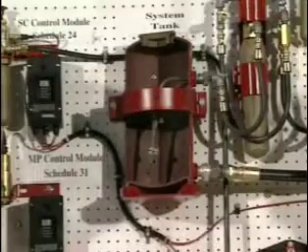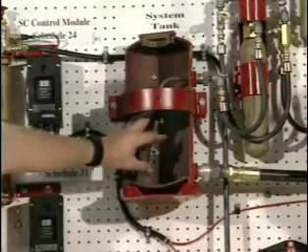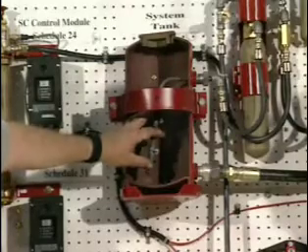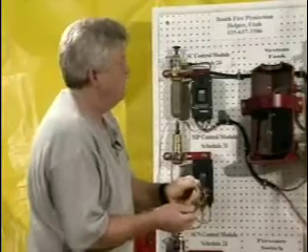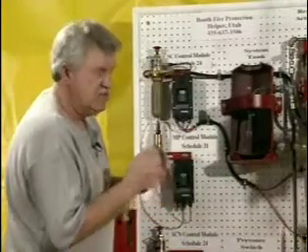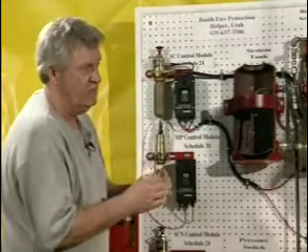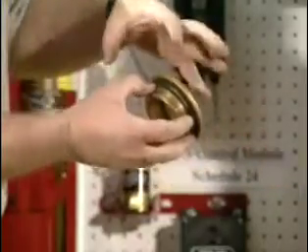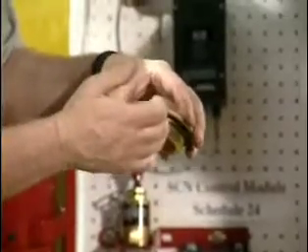Right. And the only time the siphon tube comes out is if you can physically see damage on a 6-year or on a hydro. You have to take it out for a hydro when you hydro test them. Hydro being hydrostatic? Hydrostatic testing, you have to take that siphon tube out. And there's a gasket that fits on a groove on the cap itself. This cap does not have to be gorillaed down. You can hand tighten the cap, and that's sufficient for this system. The groove is designed so that if there's excess pressure in that tank and you start to remove the cap, it will relieve the pressure long before the cap comes off.